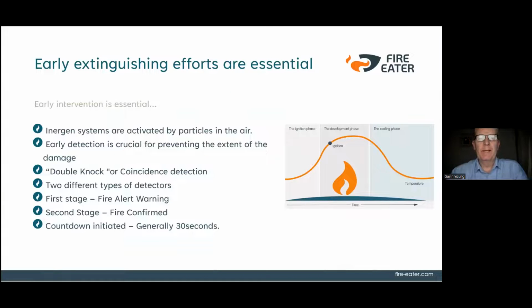Early extinguishing efforts are essential. So basically what that means is the earlier you detect a fire, the better. So the earlier the discharge into a risk when the fire hasn't taken hold, the better. So obviously you need a smoke detector to activate. It's done via what we call a double knock or coincidence type detection. So it's two different types of detector. Sometimes it's an optical smoke detector and a multi-sensor. It used to be an ionization sensor. So you use two different types to pick up different types of fire.